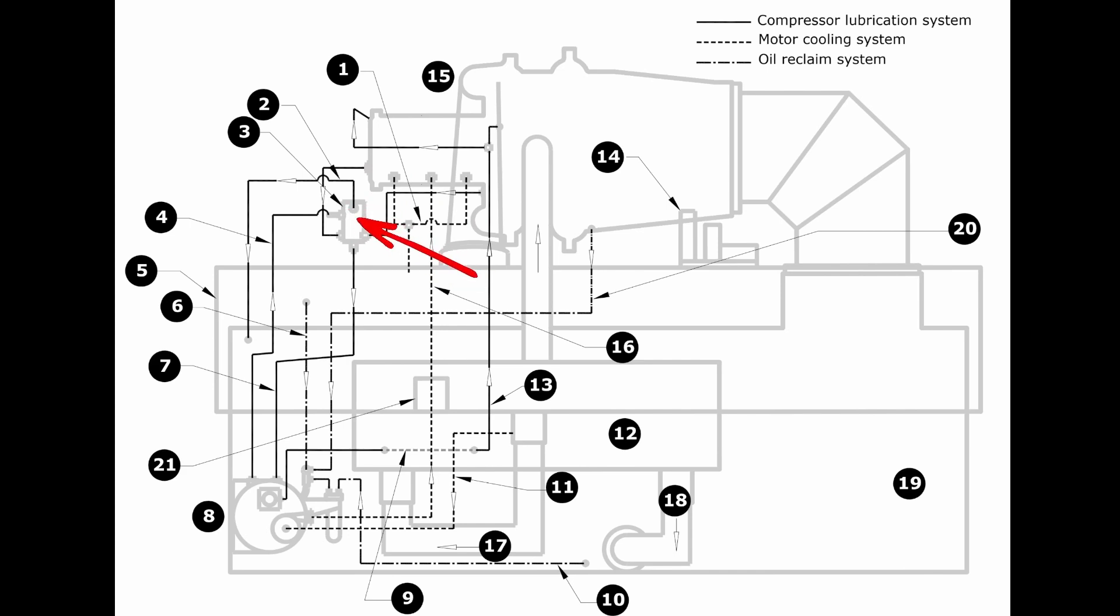A lot of things are happening in this oil separator, but any additional refrigerant that gets collected in the oil has a chance to be separated out and return back to the evaporator.